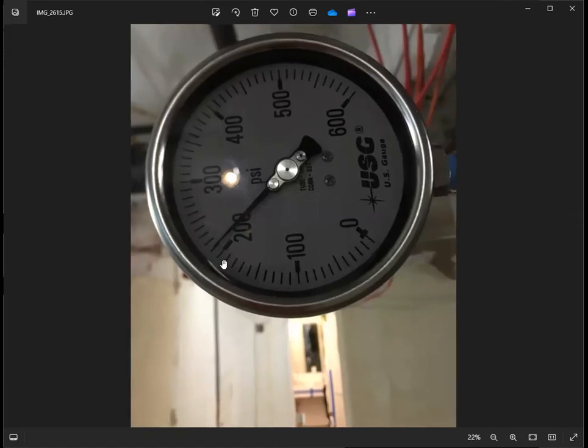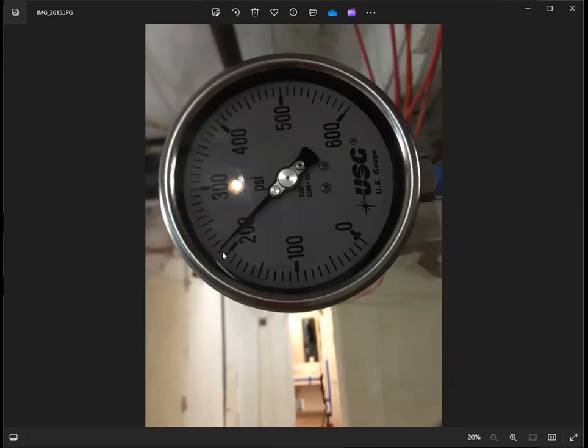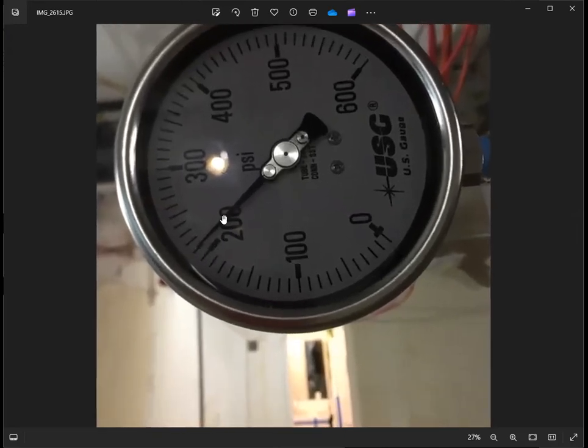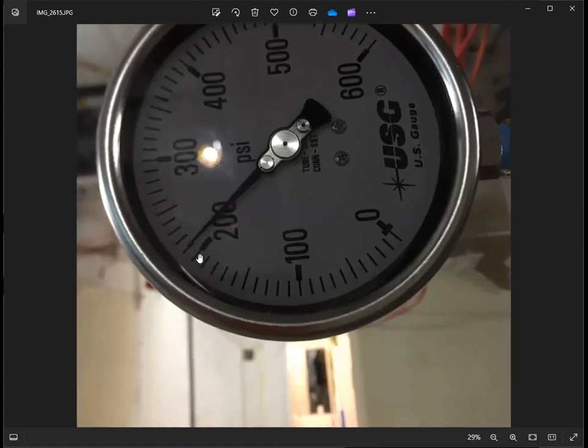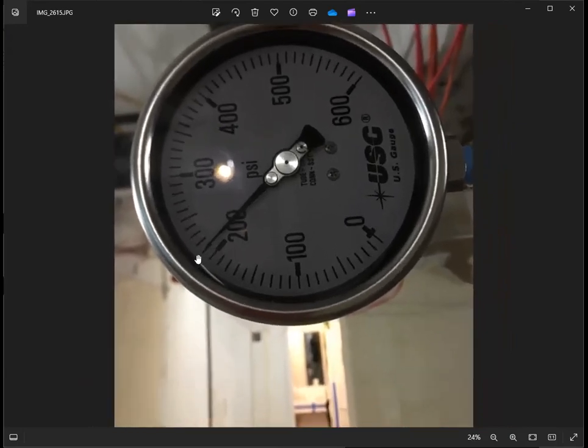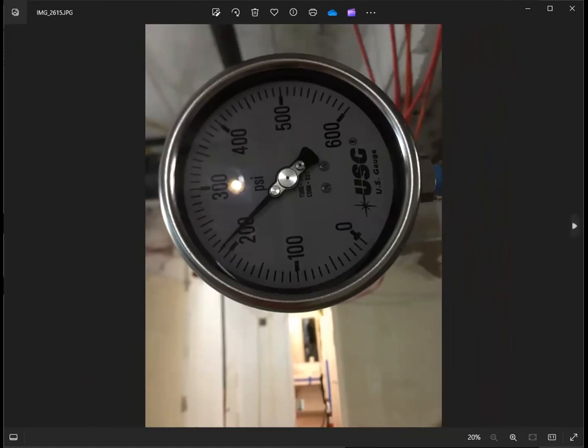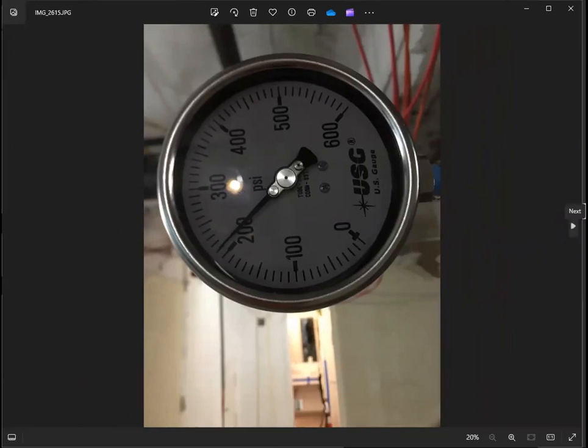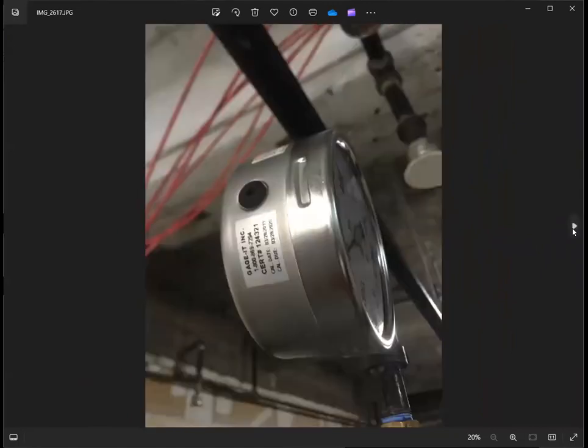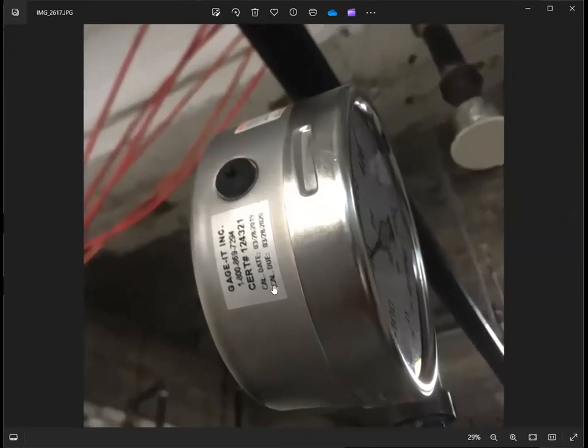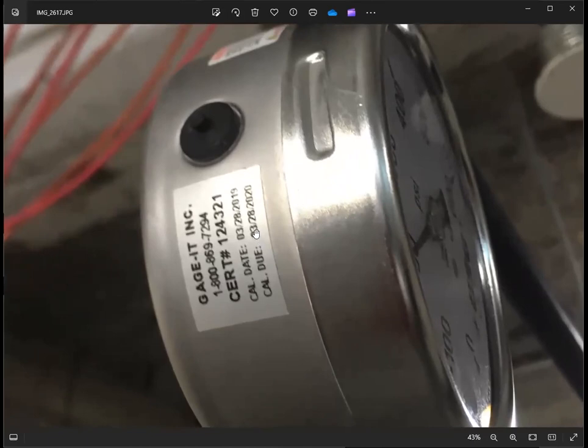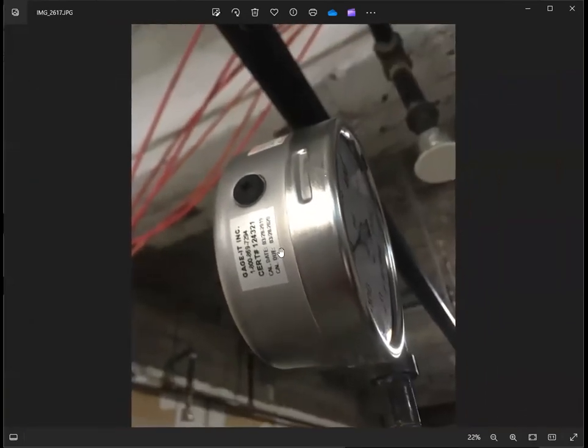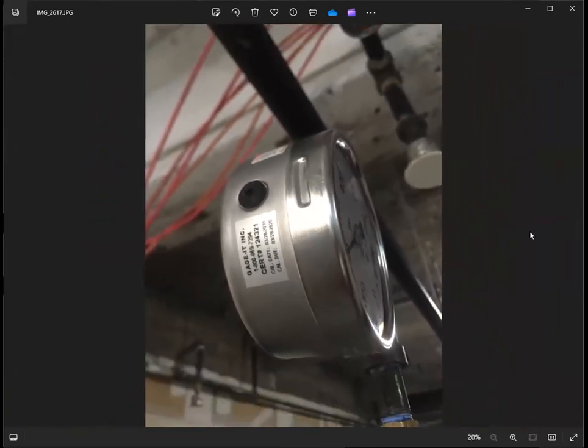As I said, take a photo closely of the gauge up close like this so you could identify if the hand, the dial of the gauge will retain and will not have a certain pressure drop. So take note of this. I'll show you later how you're gonna have an exact 2-hour test for this photo. And then I also check the calibration for this pressure gauge, the calibration cert, so the sticker. As long as you're not due, this is like 2020. I took this photo during those years, between 2019 and 2020 inspection.